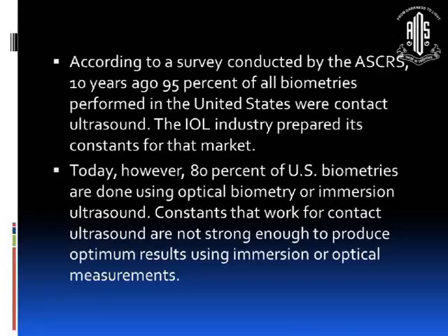According to a survey conducted by ASCRS 10 years ago, almost 95% of the biometries performed in the United States were contact ultrasound. The IOL industry prepared its constants for that market. Today, however, 80% of biometry is done using an optical biometer or immersion ultrasound.